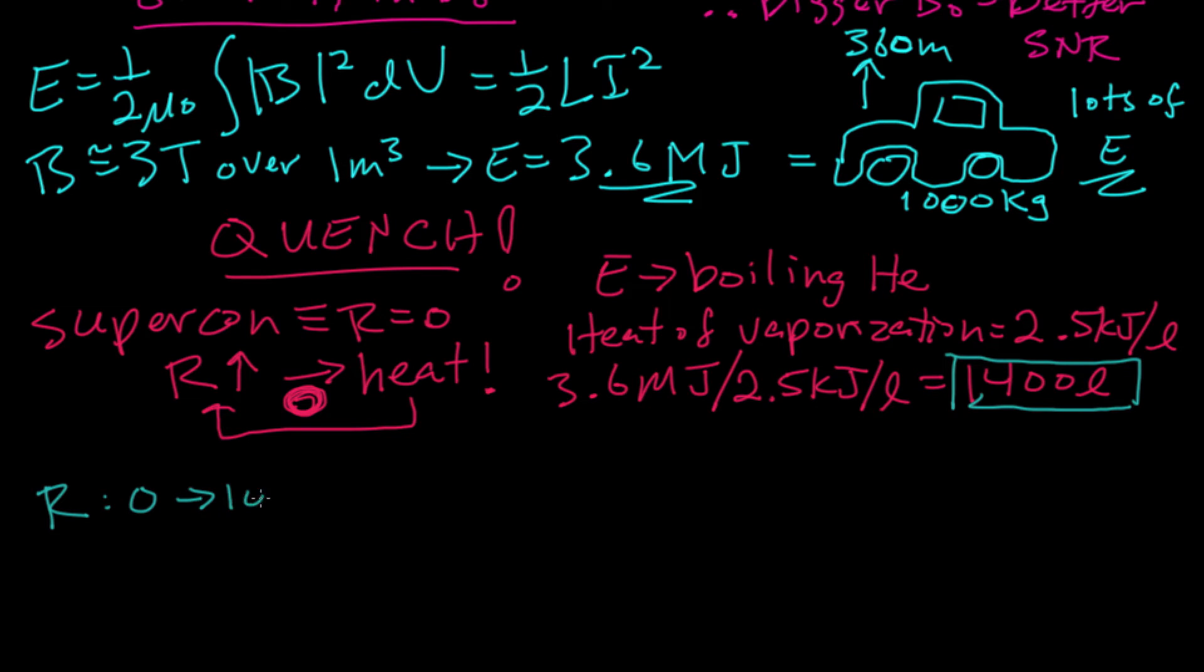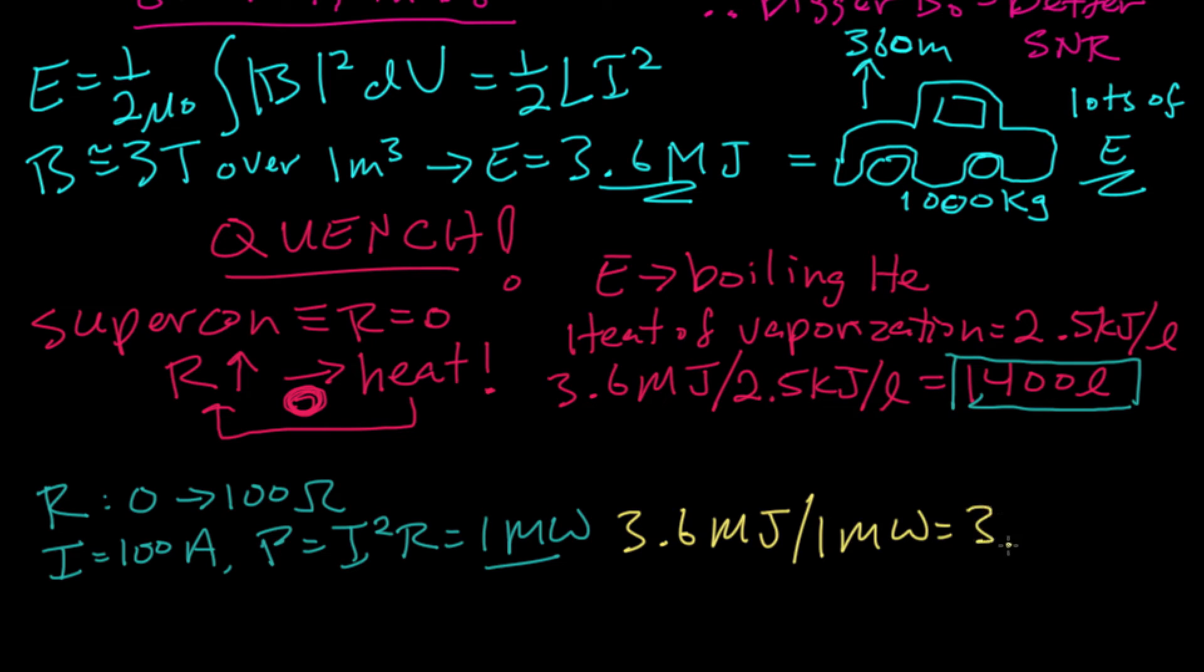When the coil becomes non-superconducting, the resistance goes from zero to about 100 ohms for that 10 kilometers of wire. For 100 amps of current, the power dissipated in that 100 ohms is about a megawatt. So roughly speaking, that 3.6 megajoules dumped at a rate of 1 megawatt can dissipate in about 3.6 seconds. It's slower than that because the current is decreasing as the quench is occurring. But roughly speaking, that 1,400 liters of liquid helium is converted into about 1,000 times that, about 1.4 million liters of helium gas in a matter of seconds. So the management of the stored energy is one of the main engineering limitations to how high the main field can be.